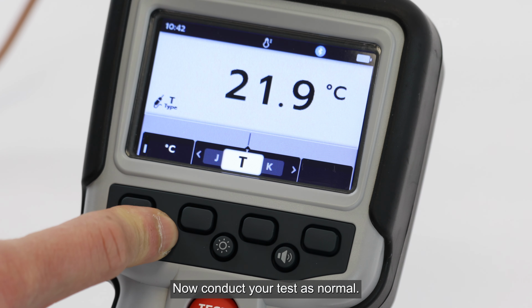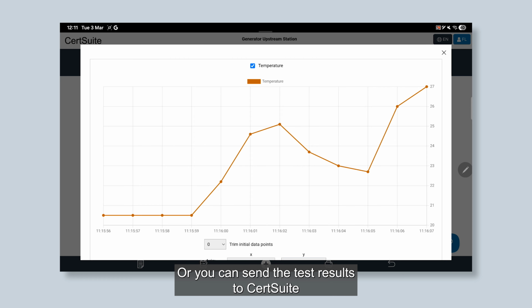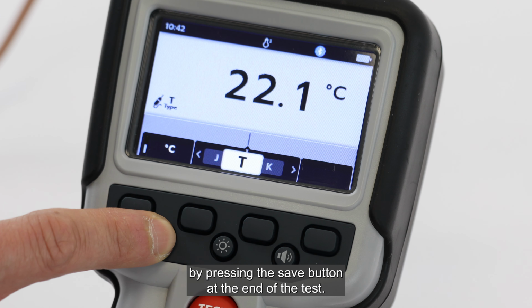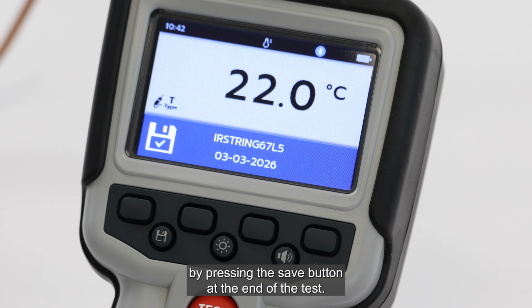With CertSuite, you can live stream and monitor results as data comes in by pressing the Save button for 3 seconds before you begin the test. Or you can send the test results to CertSuite by pressing the Save button at the end of the test.